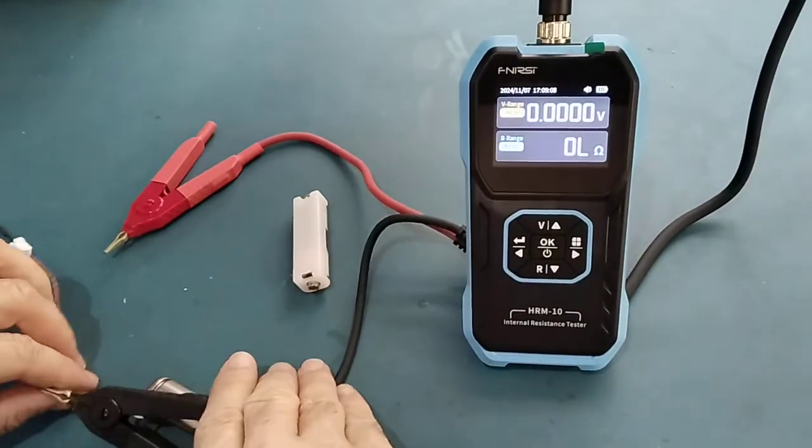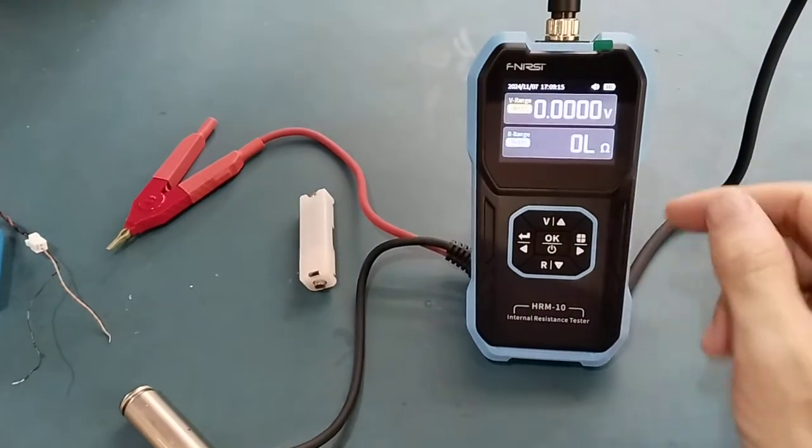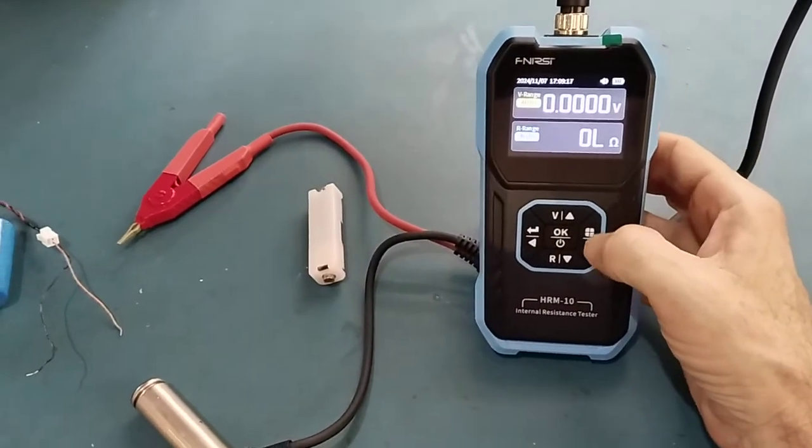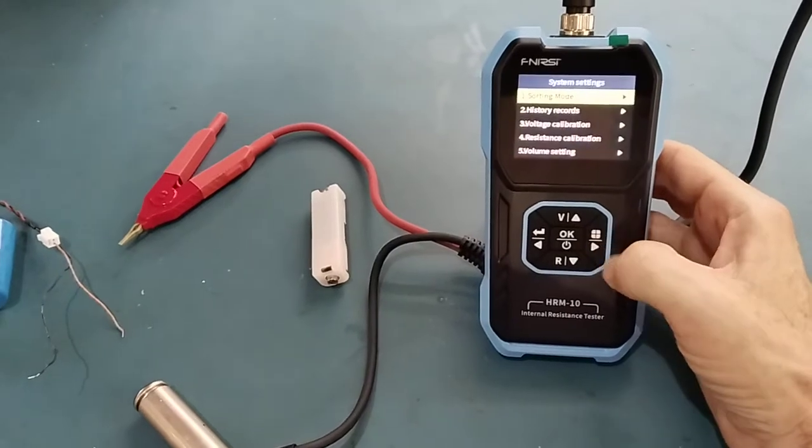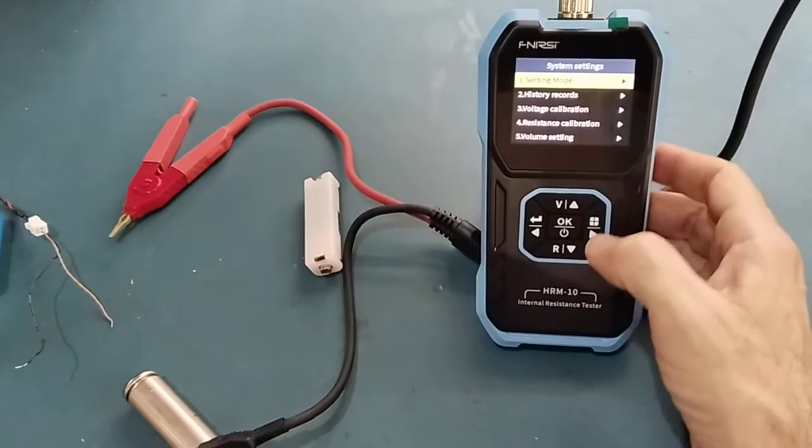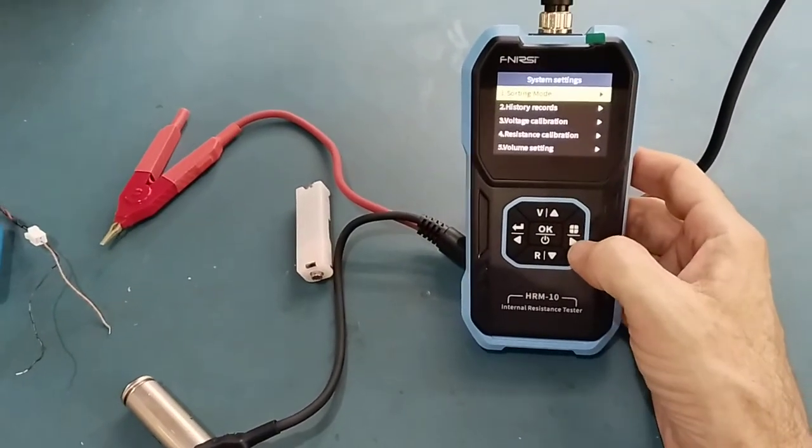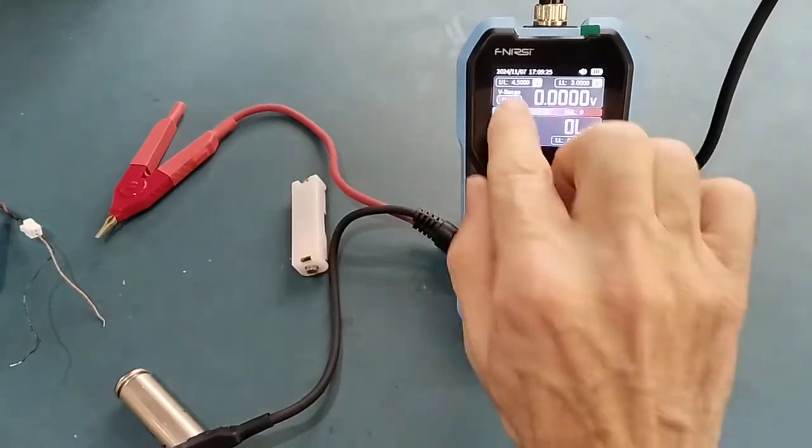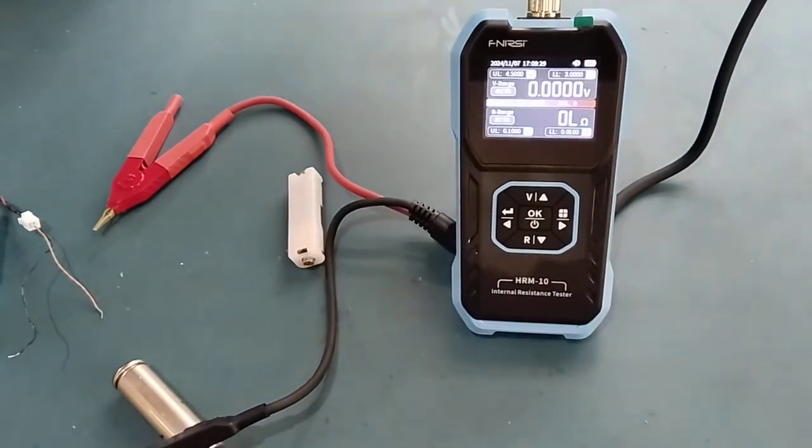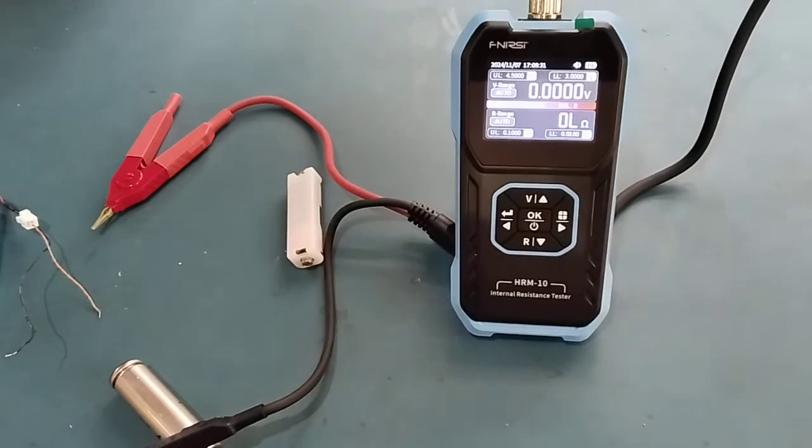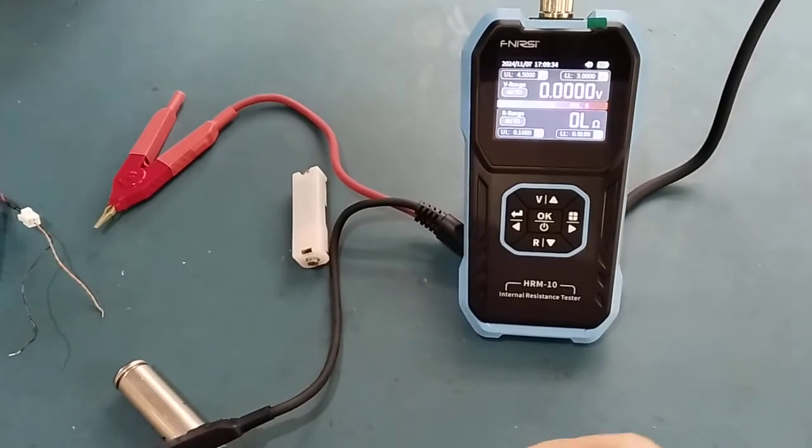You can also use this meter to automate tests for batteries. For that, you enter the menu and go into sorting mode, then set the criteria. In a production line setup, you can quickly go through batteries and sort them according to good and bad.